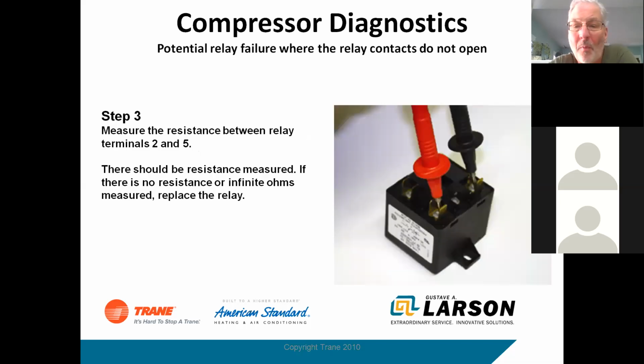The next thing you want to do is ohm out terminals 2 and 5. That's your coil relay. That's what you energize to open those contacts. If that's open, you definitely want to replace that relay because it's burned out at that point, and it won't take itself out of the circuit. And that's typically what will happen is if the start relay fails, the coil will fail, and it won't take itself out of the circuit, and you'll see capacitor failures. So if you see a capacitor failed on a start relay and you're not sure what the cause was, just replace both of them. Don't replace just the capacitor, replace the relay and the capacitor.